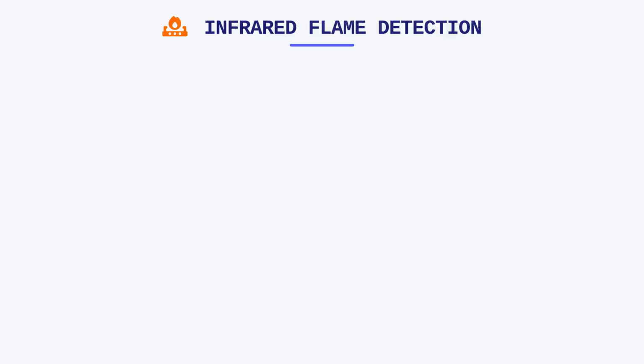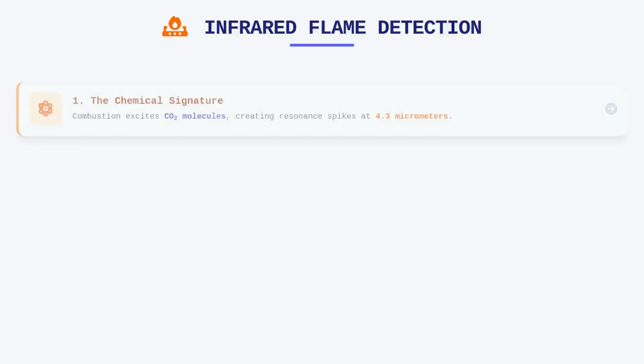Infrared sensors, on the other hand, operate by detecting the thermal radiation emitted by carbon dioxide molecules in the flame. As a hydrocarbon fuel burns, the combustion process excites the CO2 molecules, resulting in resonance spikes at specific infrared wavelengths, typically around 4.3 micrometers. This is a robust method because flames of this type will always produce this specific signature, regardless of the ambient air temperature or the presence of other heat sources.